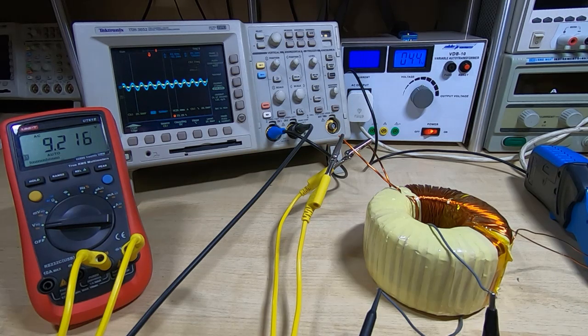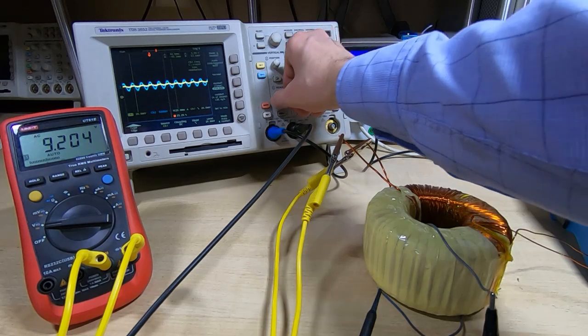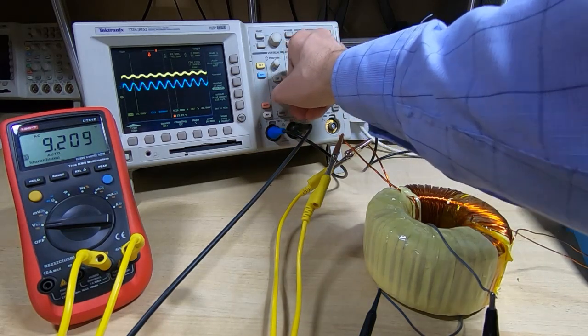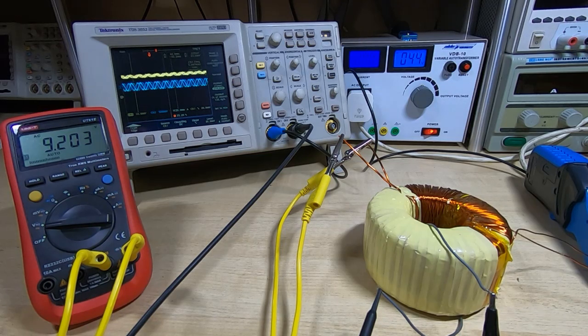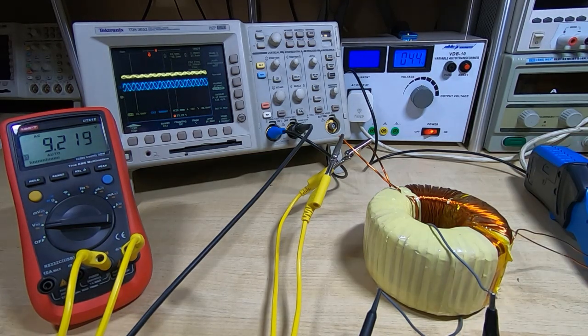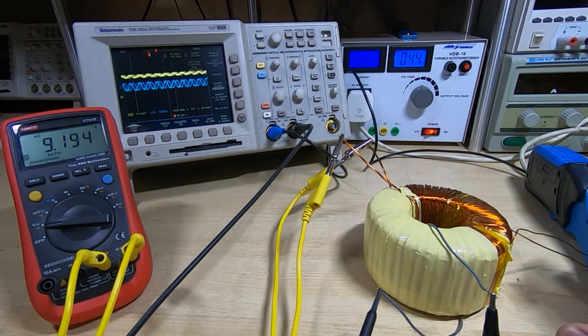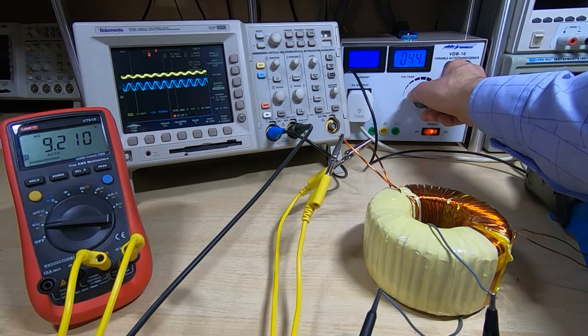Notice on the scope, that's on channel two, we're getting the AC signal which is just the AC power coming out of the transformer. That's the AC voltage and you can see it's showing a quite nice sine wave. On the current clamp you can see that at the moment we're getting a very small signal, almost nothing, and that's what we expect. We shouldn't be seeing large currents at this voltage because we're nowhere near saturating the core, so I'll continue to increase the voltage.